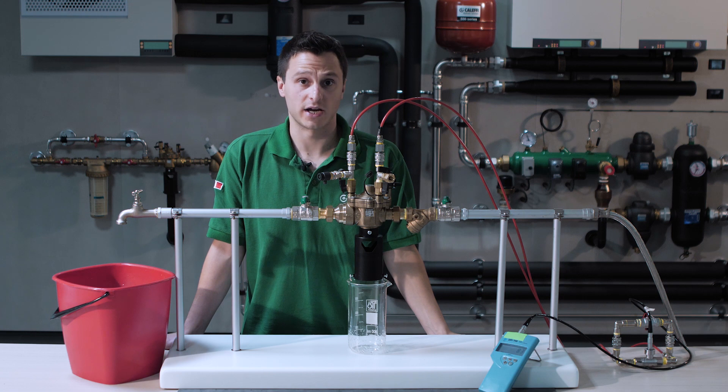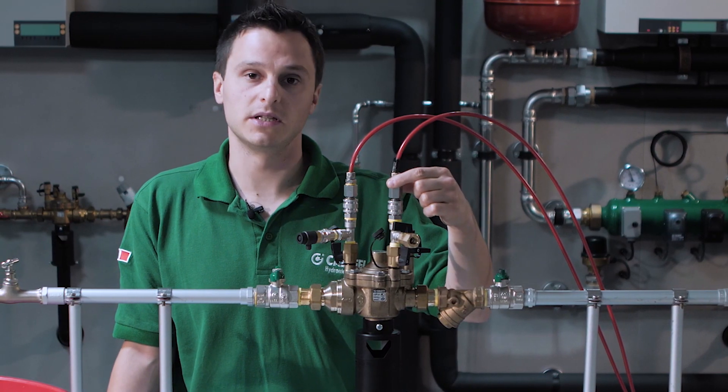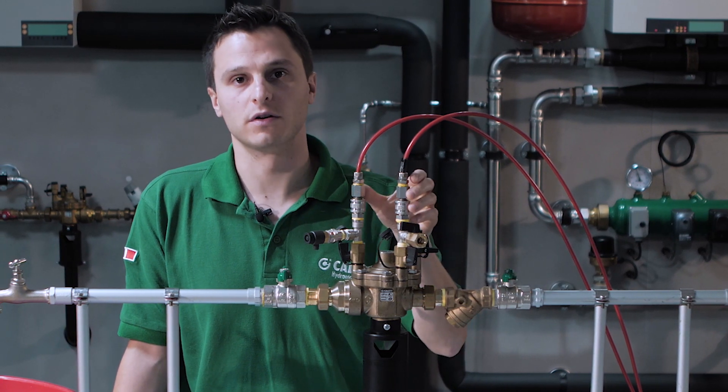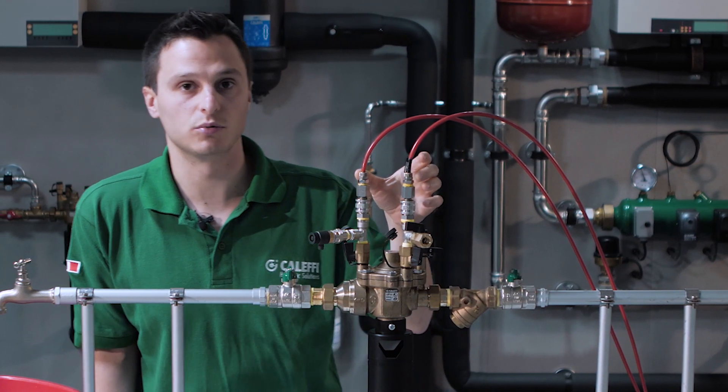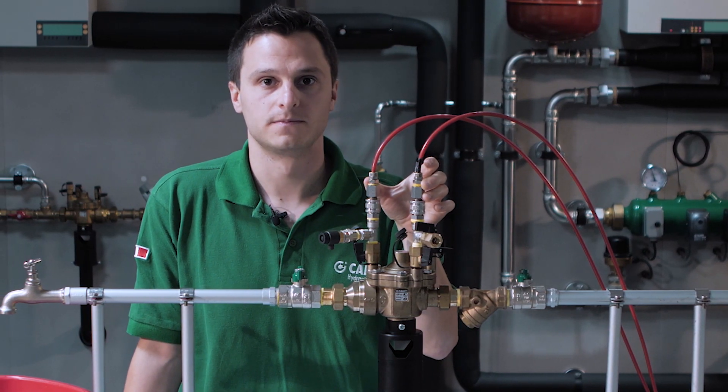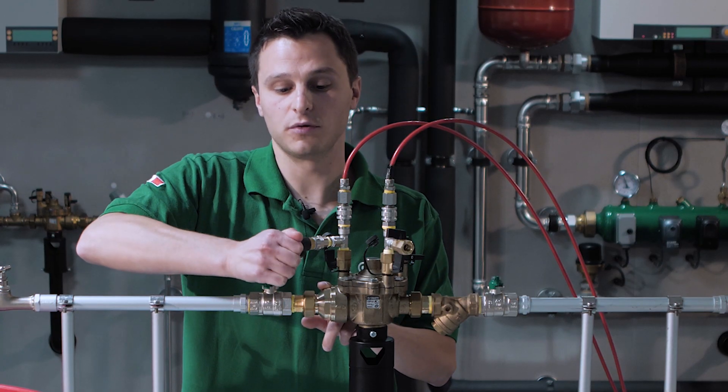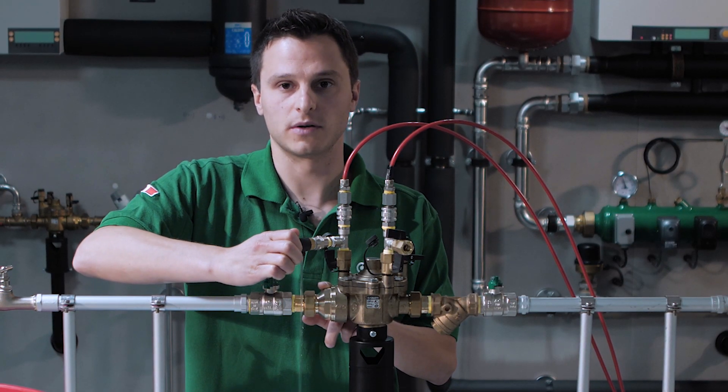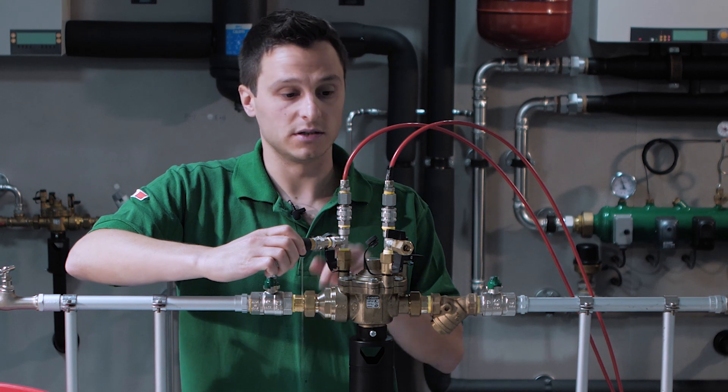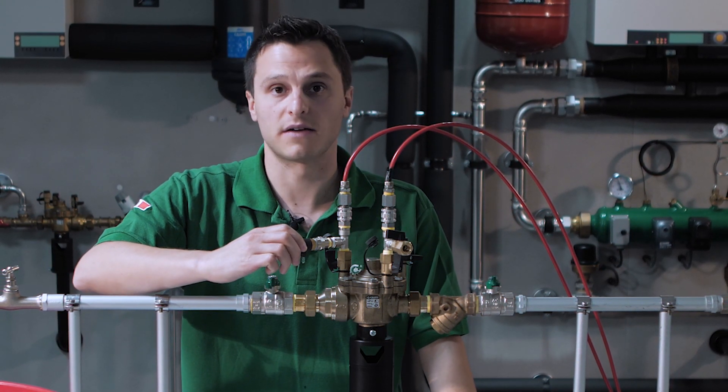For the last check, connect the differential manometer to the intermediate chamber and downstream area. Verify that the differential pressure between these two points is at least 70 millibar. If the downstream check valve operates correctly, the differential pressure must remain at least 70 millibar even when decreasing the downstream pressure.